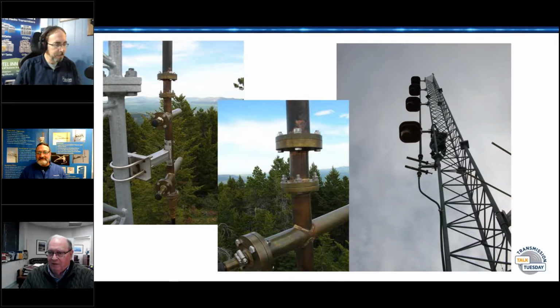Even with a camera like Jeff showed that you can put on the bottom of your iPhone or Samsung phone, you can scan the tower, preferably at night when the sun loading and thermal mass loading has gone down. Is anything looking at a different temperature? Look at it from different angles, because sometimes it's just wind blowing - but do you see it that way? When you have a tower guy on site, have him go up with even a little thermal gun, because your skin can't really determine temperature differences - it has to be a big difference for your hands to pick it up. But a thermal gun or camera like Jeff showed, just take pictures as they go up until they have to turn it off. Just look for thermal differences - thermal means loose, means something's wrong, means something's going to burn up.